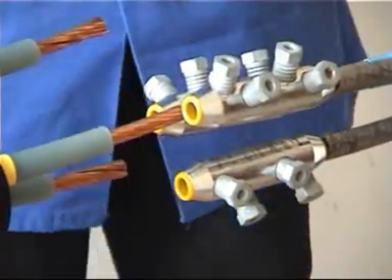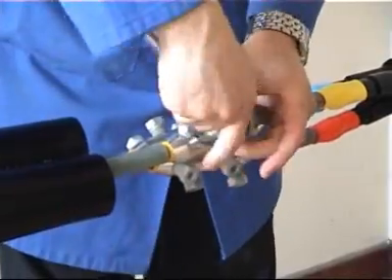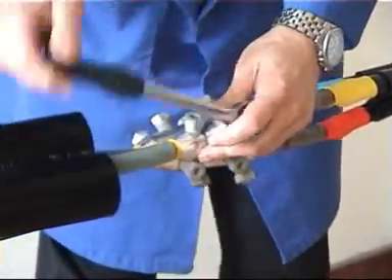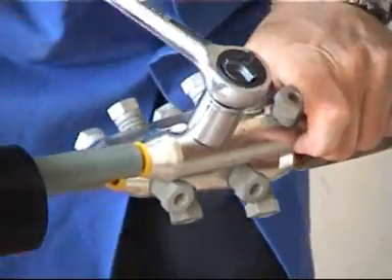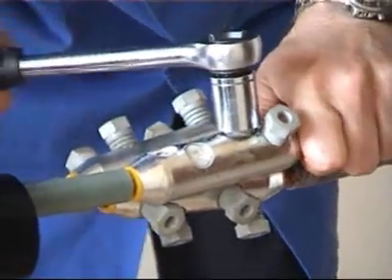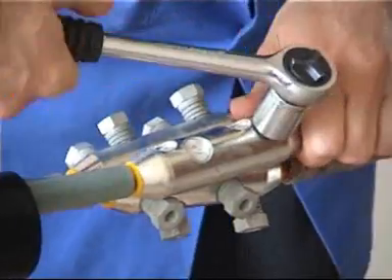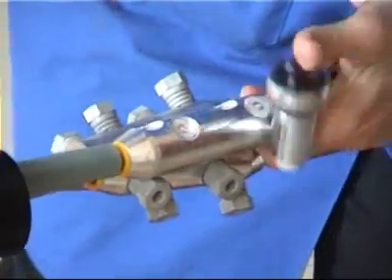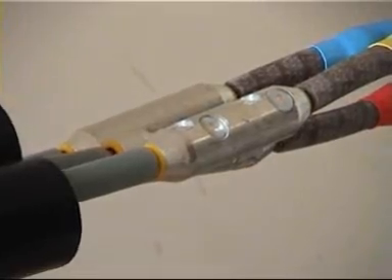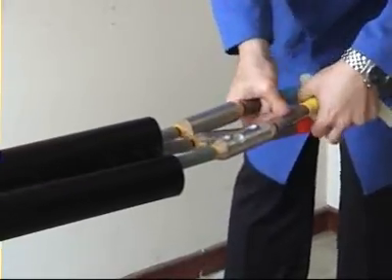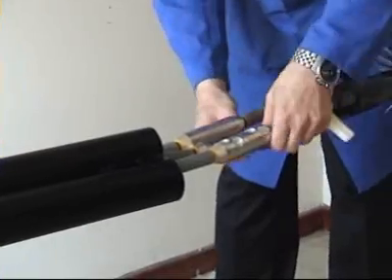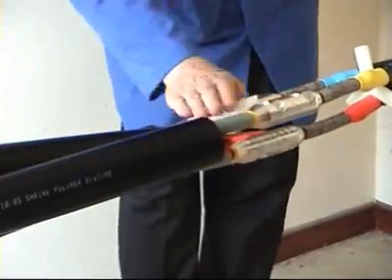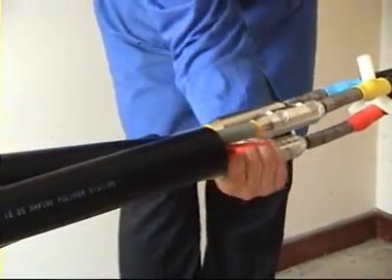Users should refer to the instruction sheet supplied with the connectors. We have a core cross on this cable. We're also spacing out the cores to allow the connector insulation tubes to slide over the connectors. Before doing so, use cable cleaning tissues to degrease the connectors and primary insulation.